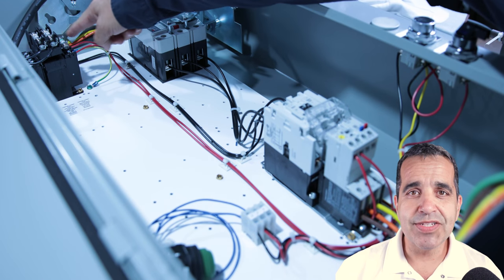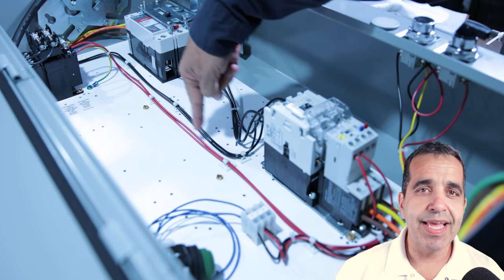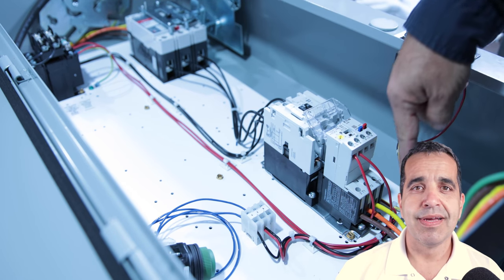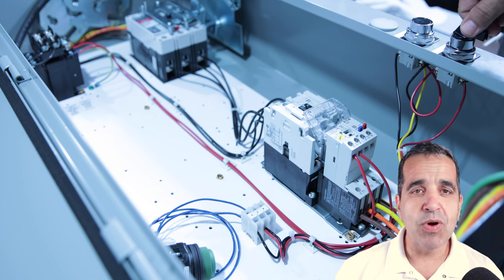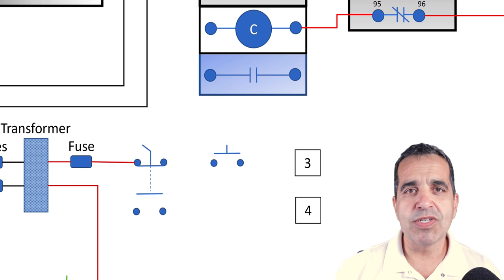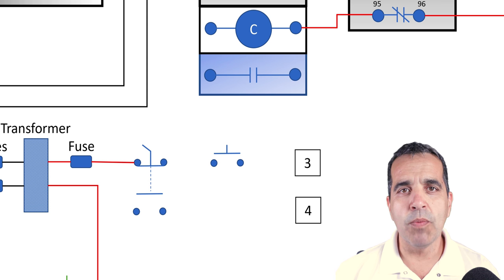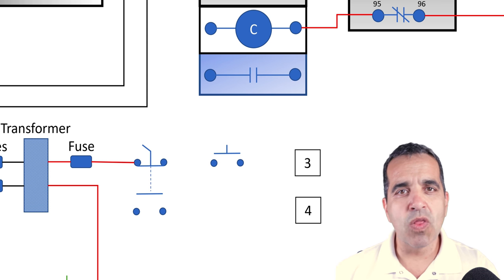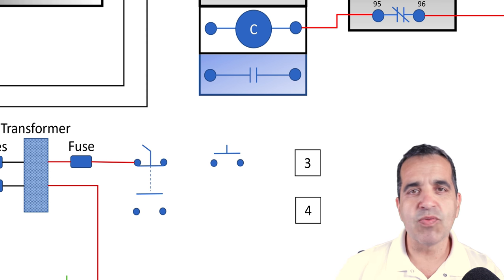On this drawing, we're showing it in the hand mode. You can see the hand mode is closed, the auto mode below is open. When you flip the switch to the middle, both contacts are open. When you switch all the way to the right, only the bottom switch is closed.